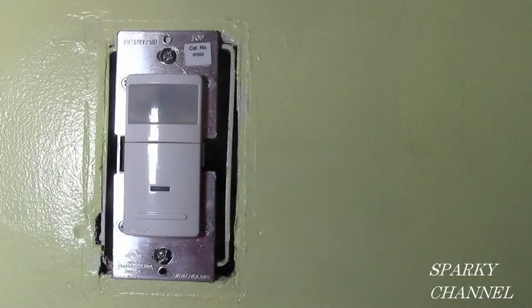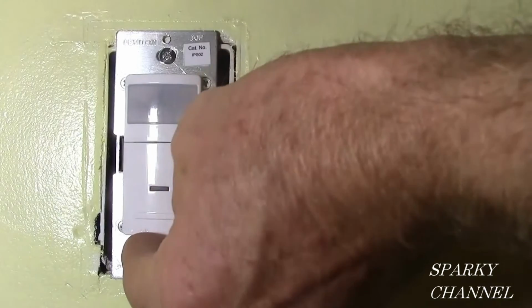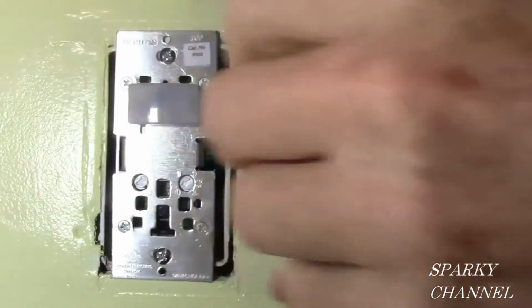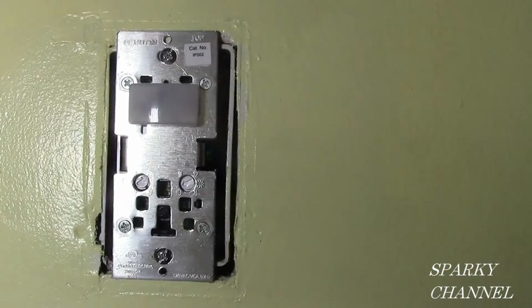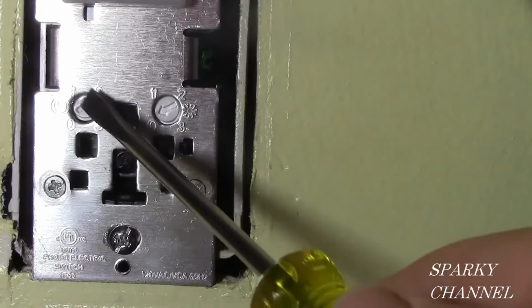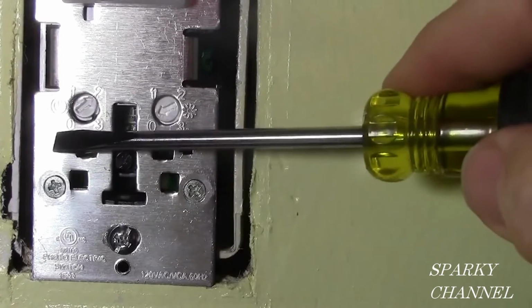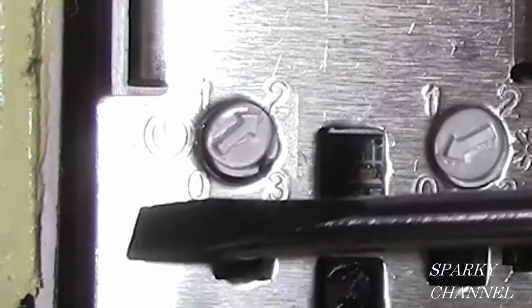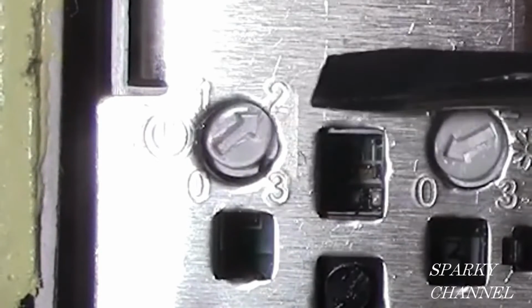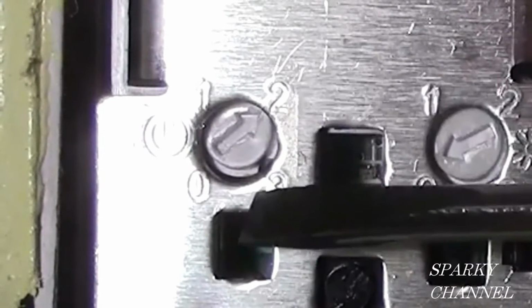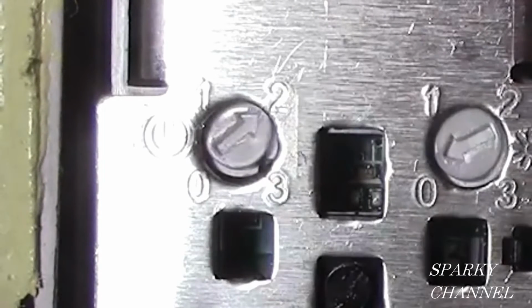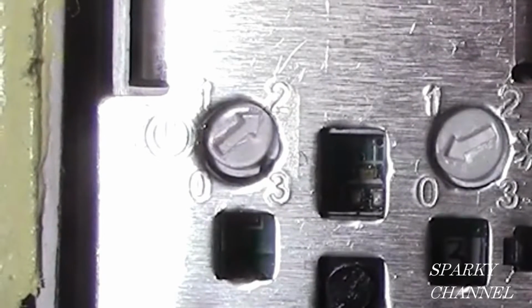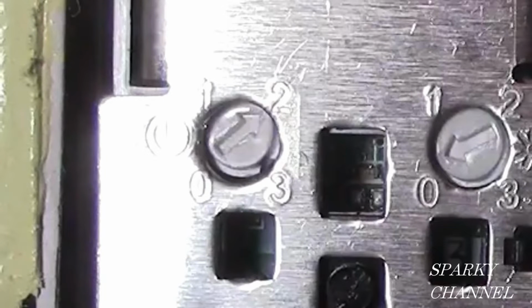The next thing we're going to do is program the IPS02. And to do this, you take off the plastic cover. You pull it from the bottom, and it has 4 little pegs that go in the holes, and it comes right out. Notice there are 2 plastic dials. The first one here on the left is your time selector. This is the amount of time that you would like your light to stay on after people have left the room. The 0 setting is for 30 seconds.